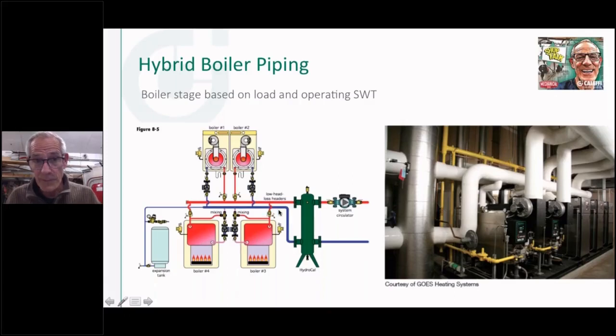As long as this header pipe is sized big enough for all the loads connected to it, this becomes the point of no pressure change reference for this pump, this pump, this pump, and this pump, through the header, through the separator to that pump. So it really frees you up for a lot more creative expansion tank location when you have a separator with all those different options, those 4 ports that you could connect into.